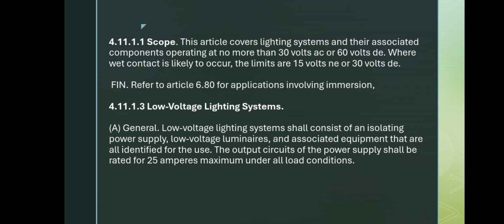This system must not exceed 30 volts AC or 60 volts DC, but when there is possible contact with water or moisture, the allowed limit is lower: 15 volts AC or 30 volts DC. For installations involving immersion in water, we refer to Article 680. Second, the low-voltage lighting system. In low-voltage lighting systems, three main components are required: an isolating power supply, low-voltage luminaires, and other equipment that are identified and approved for low-voltage use. The output of the power supply must not exceed 25 amperes regardless of the load.